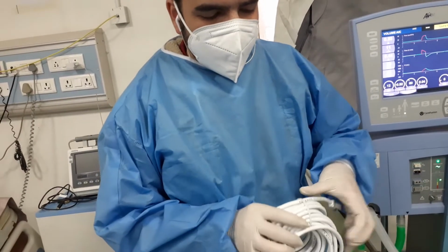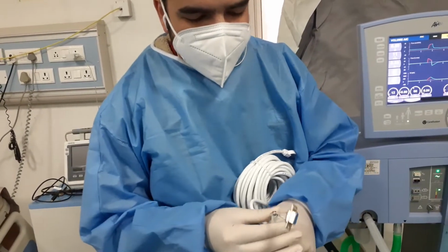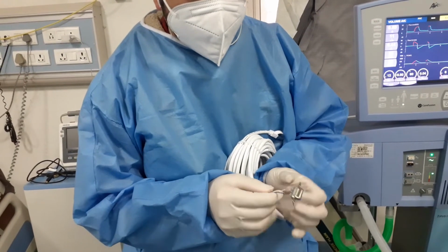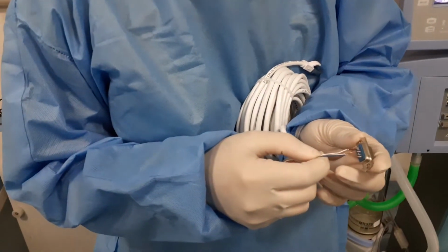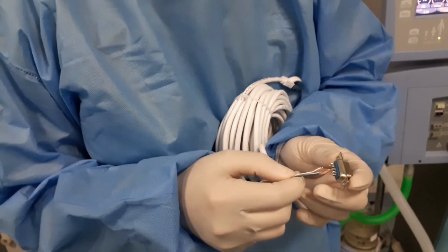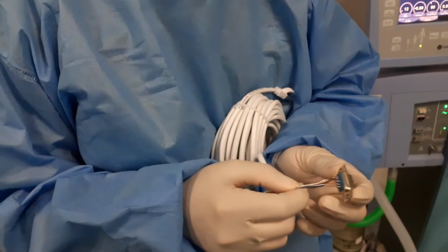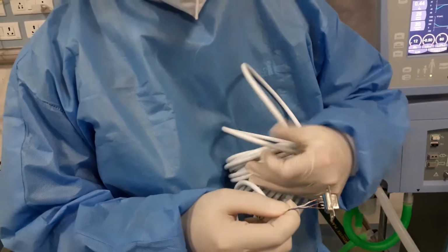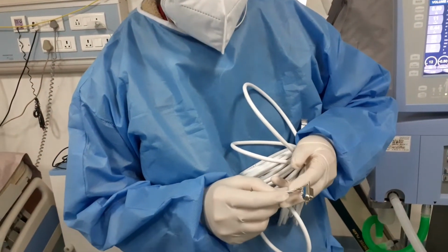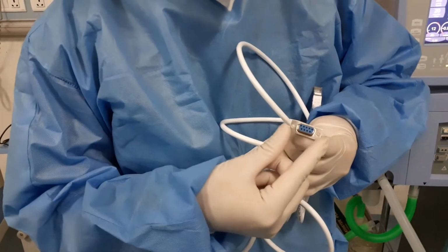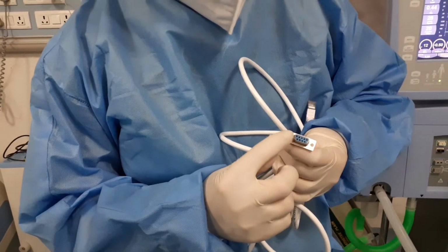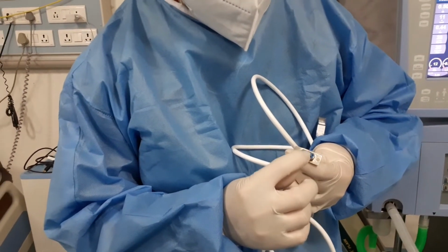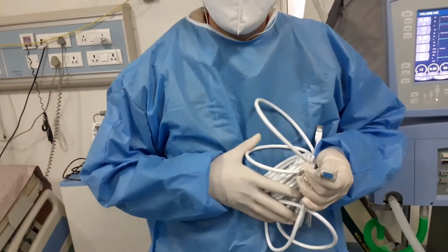On the other side also it was RJ45, but we customized it. We removed some wires and selected only 3 wires out of it: receiver, transmission and ground wires. This depends upon what kind of pin layout is there in the AVEA, where we are going to connect this. Here we soldered it over a DB9 female port. These are pins 1 to 5, then 6 to 9. We have to attach it on pins 2, 3 and 5: receiver, transmission and ground. It depends upon the pin layout of the AVEA ventilator.